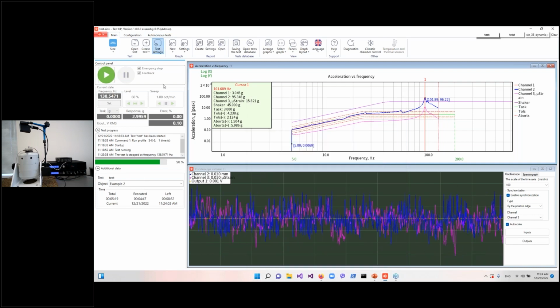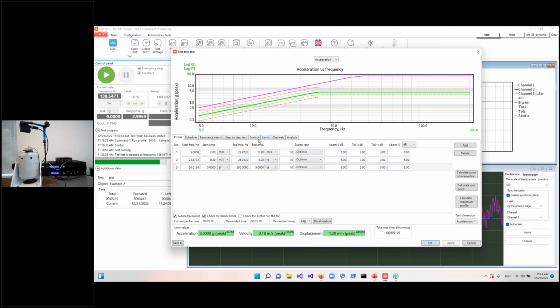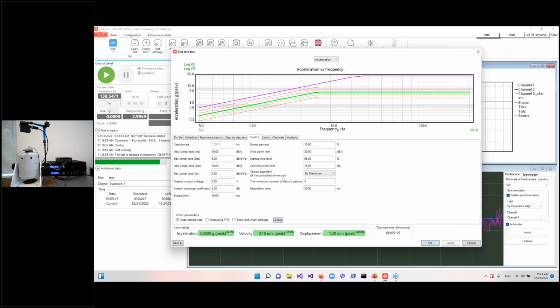So let's go back to our presentation. Sorry, I was asked about the control. Here in sine test, in control tab, you have a control switch limit option. That means that we can have a control from our start frequency up to this value, and we will control our test with a non-accelerometer sensor. For example, if we need to control the test from 5 Hz up to 30 Hz with a laser vibrometer, we select it as control and enter here our final frequency value.